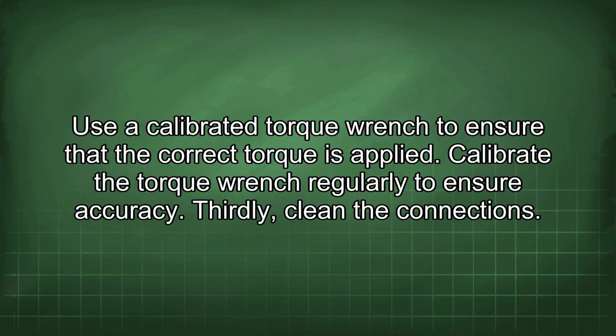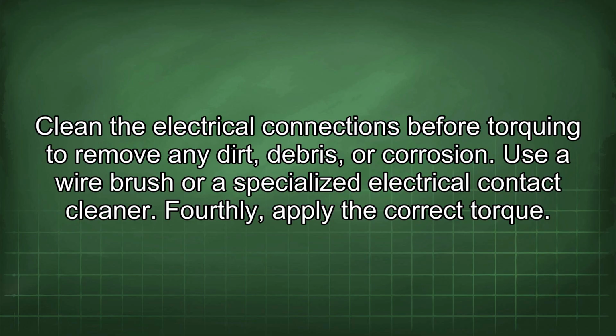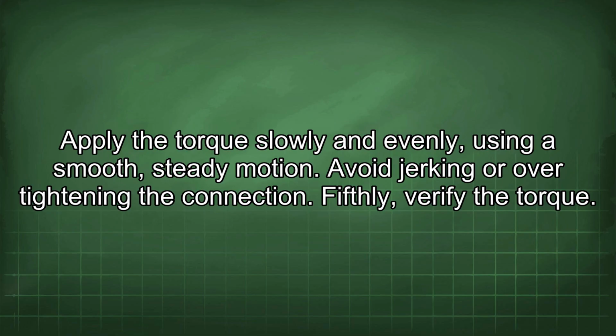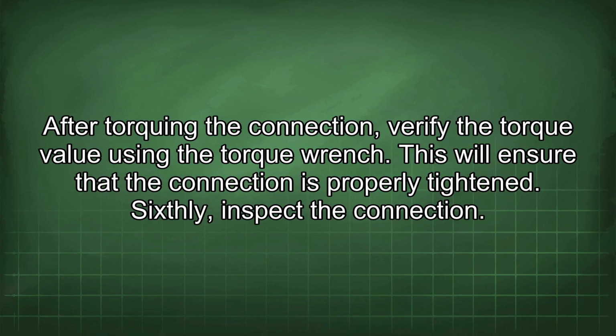Thirdly, clean the connections. Clean the electrical connections before torquing to remove any dirt, debris, or corrosion. Use a wire brush or a specialized electrical contact cleaner. Fourthly, apply the correct torque. Apply the torque slowly and evenly using a smooth, steady motion. Avoid jerking or over-tightening the connection. Fifthly, verify the torque. After torquing the connection, verify the torque value using the torque wrench. This will ensure that the connection is properly tightened.